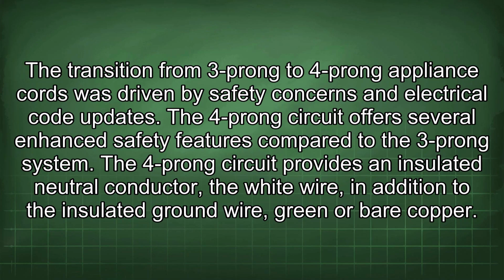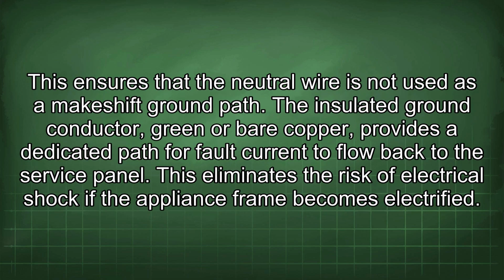The transition from 3-prong to 4-prong appliance cords was driven by safety concerns and electrical code updates. The 4-prong circuit offers several enhanced safety features compared to the 3-prong system. The 4-prong circuit provides an insulated neutral conductor, a white wire, in addition to the insulated ground wire, green or bare copper. This ensures that the neutral wire is not used as a makeshift ground path.